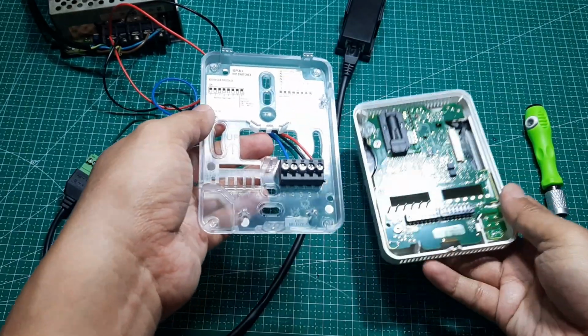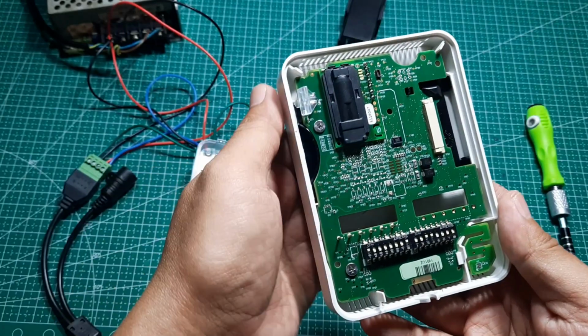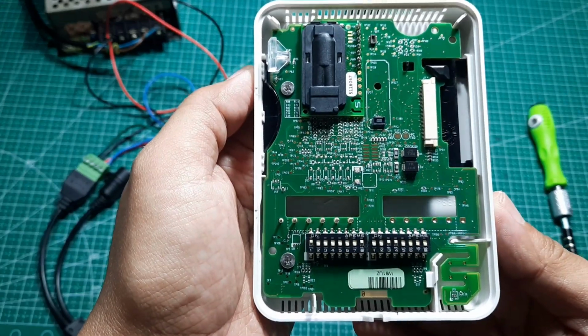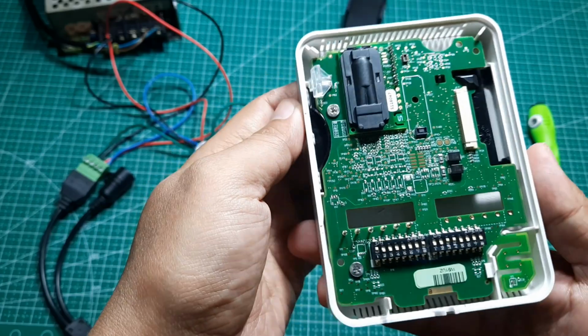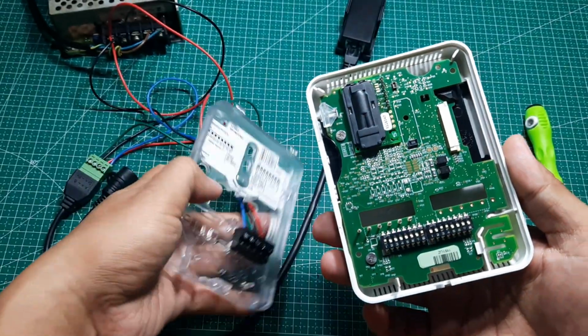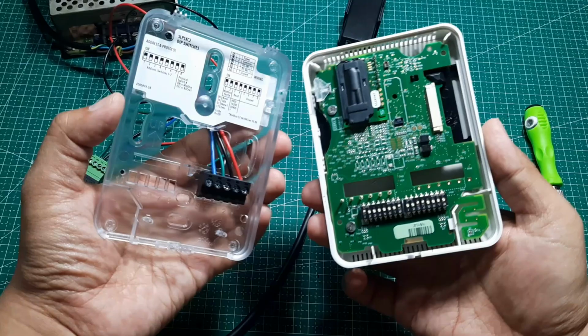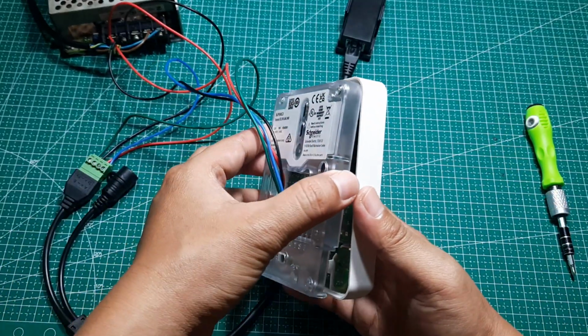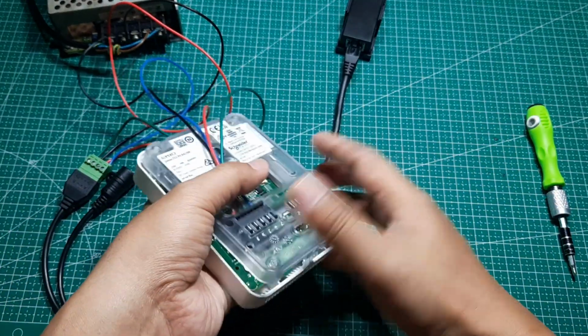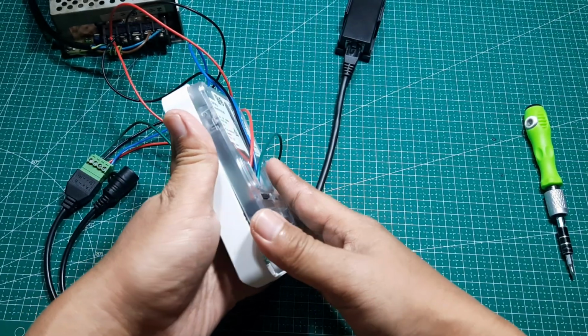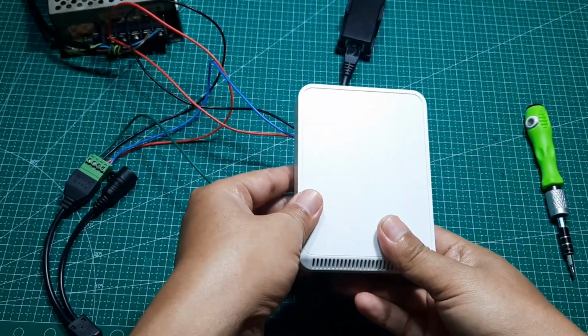Next is the configuration for the DIP switches. For the switch address configuration, I set the value to 1, which is pin 1 is on. Then, for the switch communications configuration, I set pins 3 and 4 to on to configure Modbus with a baud rate of 57,600. Next, reattach the back cover to the front part of the device.